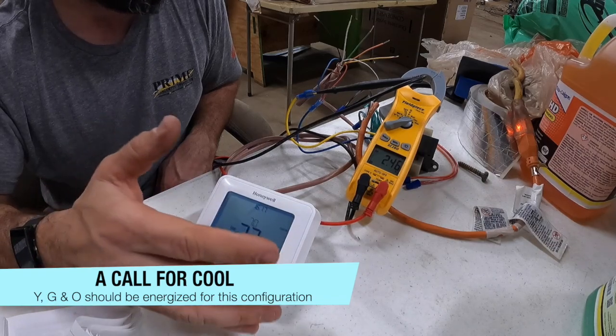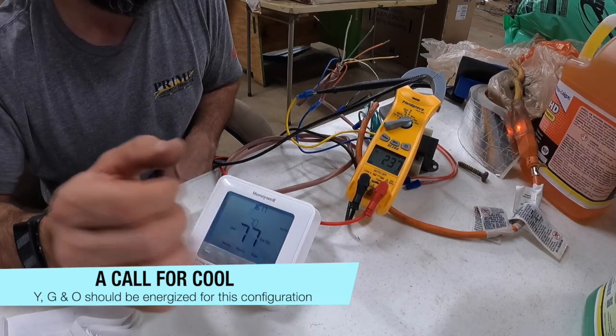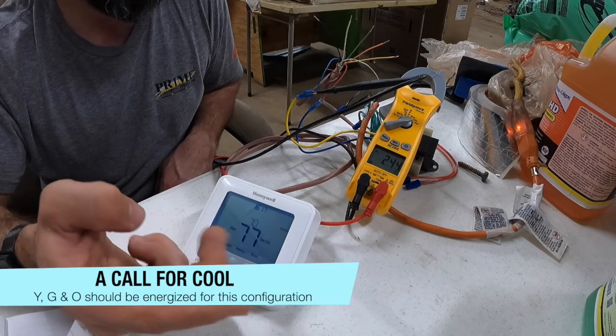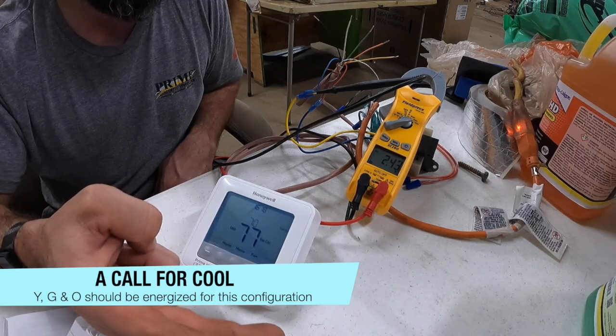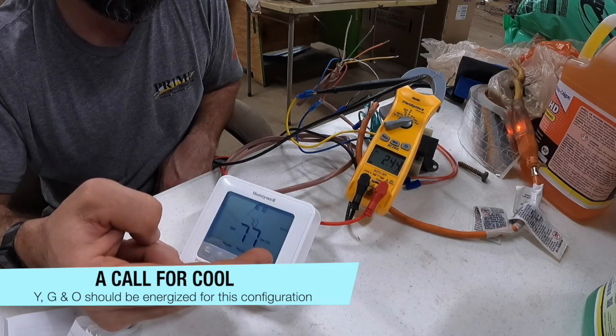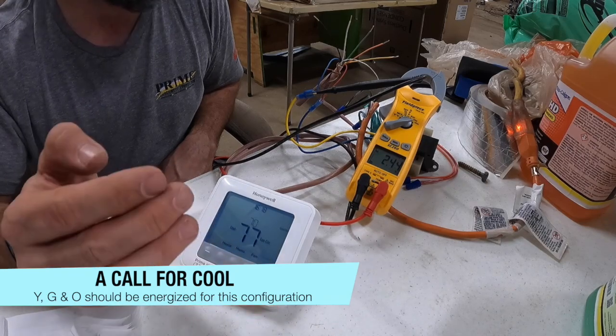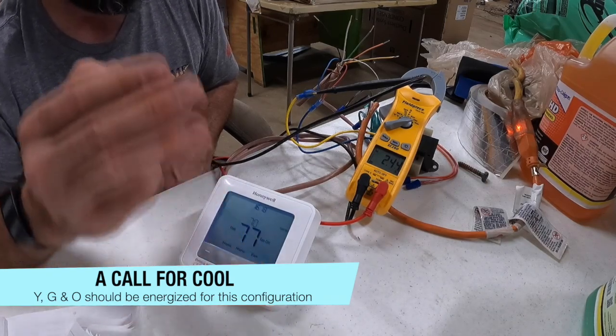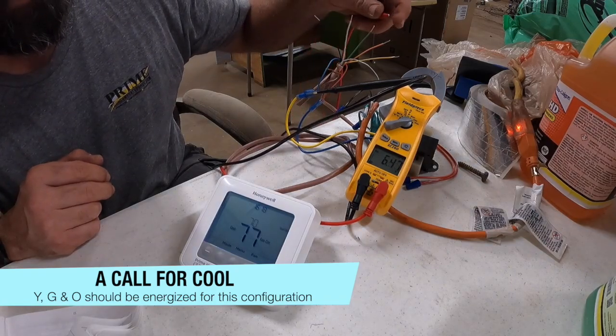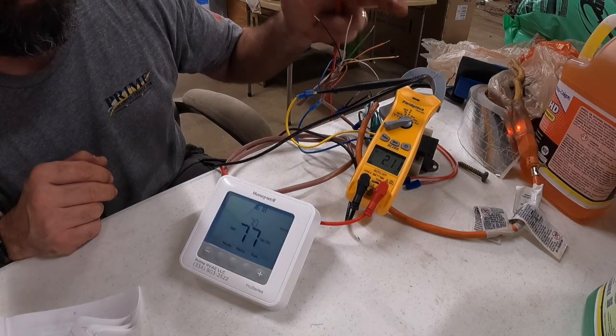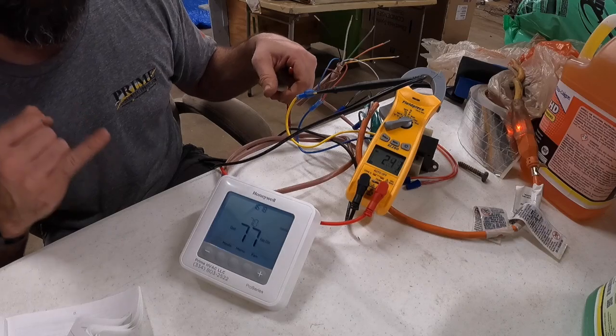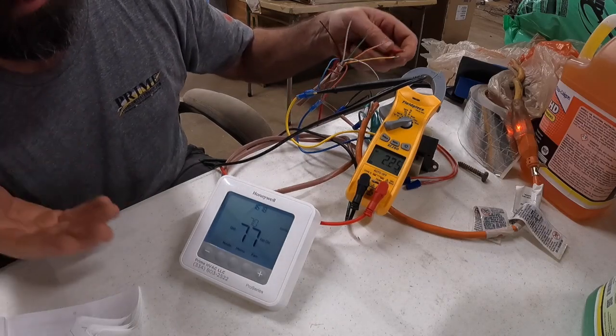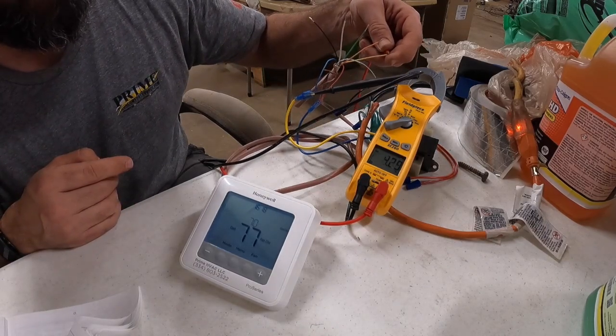So if we're going to cool the house, we need the blower fan to come on, we need the compressor and the outdoor fan to come on, which is the Y terminal, and we need to energize the reversing valve, which is the O terminal, which is going to be orange. So yellow, orange, and green, that's Y, G, and O. OB terminal on the thermostat.